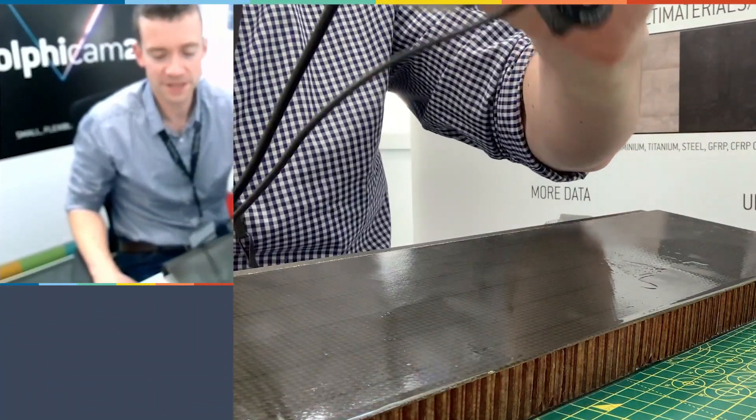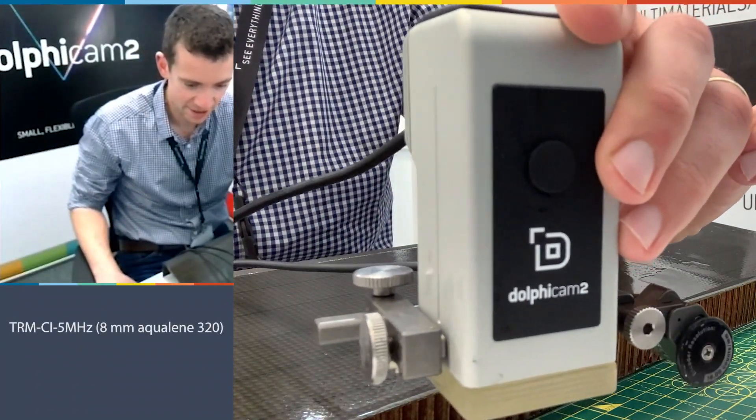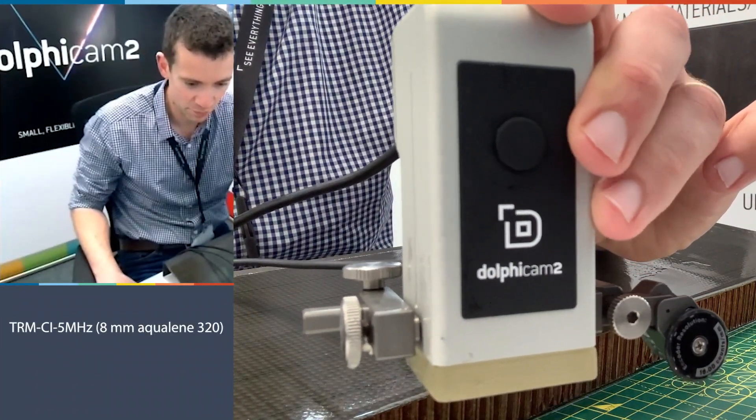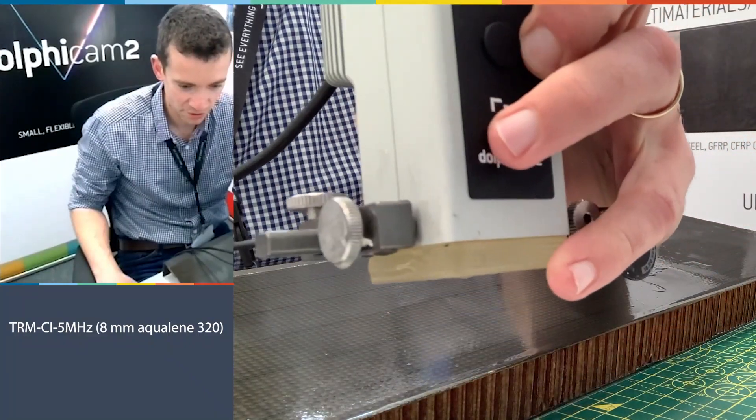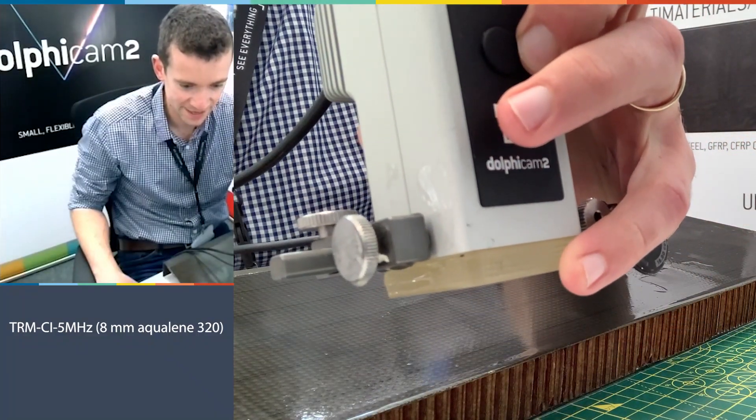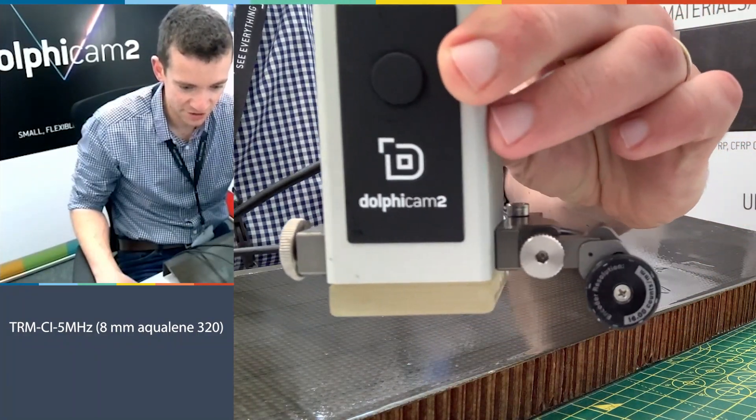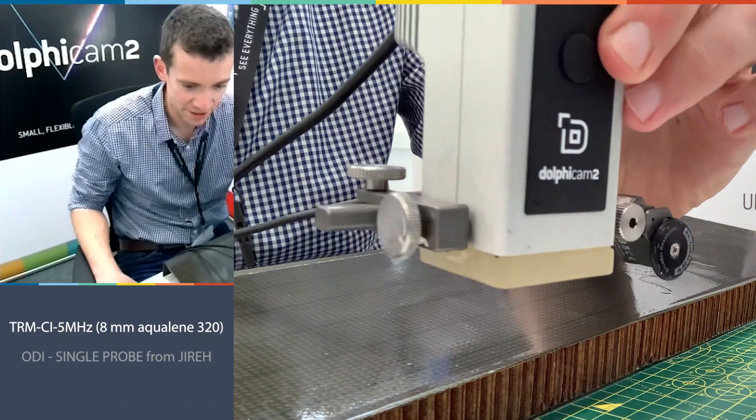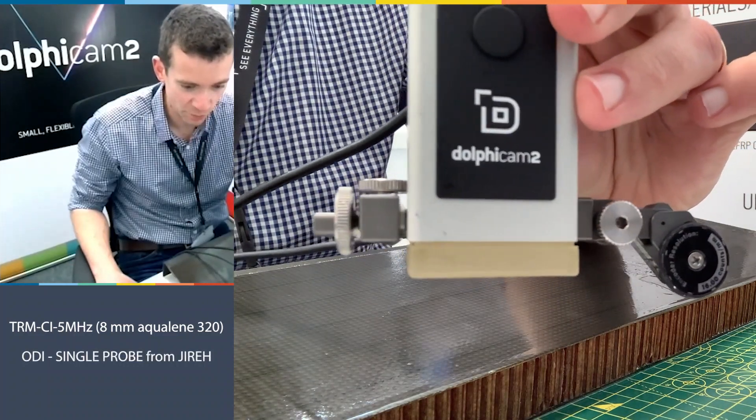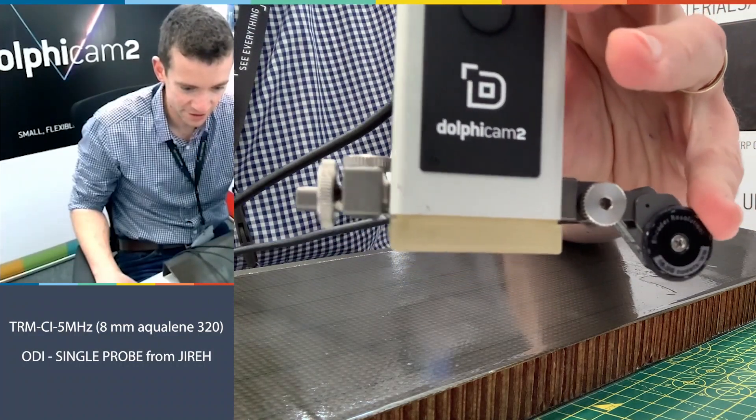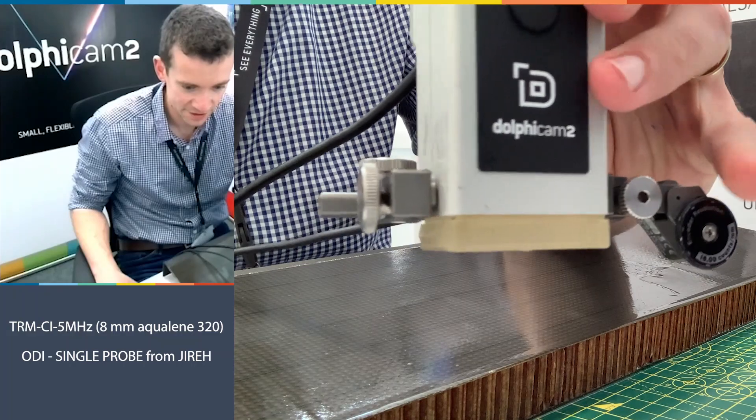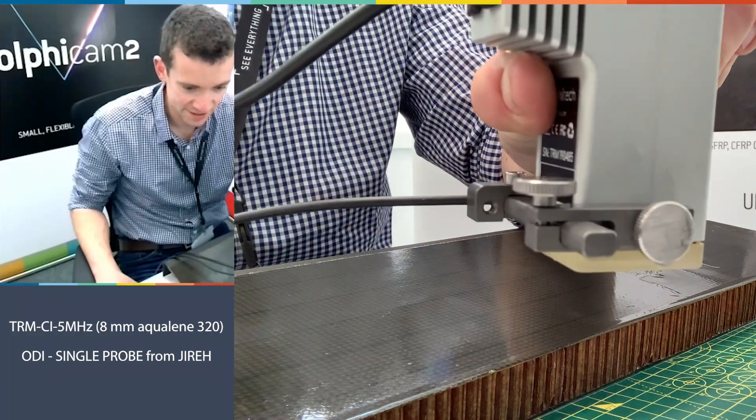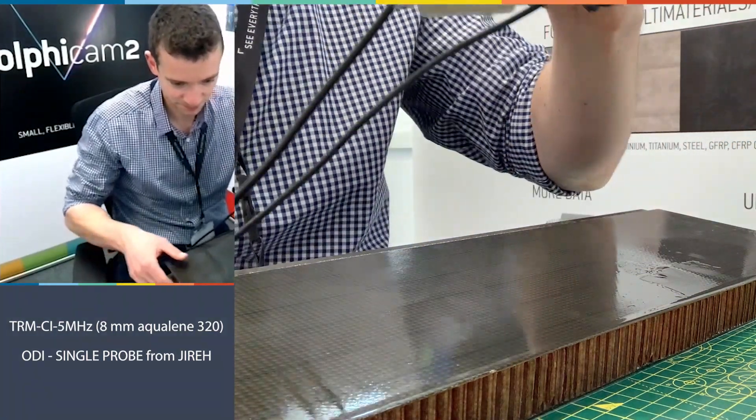In front of me today I have a CI TRM which is a five megahertz model with an eight millimeter Aqualene delay line, and you can see attached to it I have a JIREH ODI wheel encoder. Here's the wheel to encode the distance and we can see how well it fits on our TRM models.